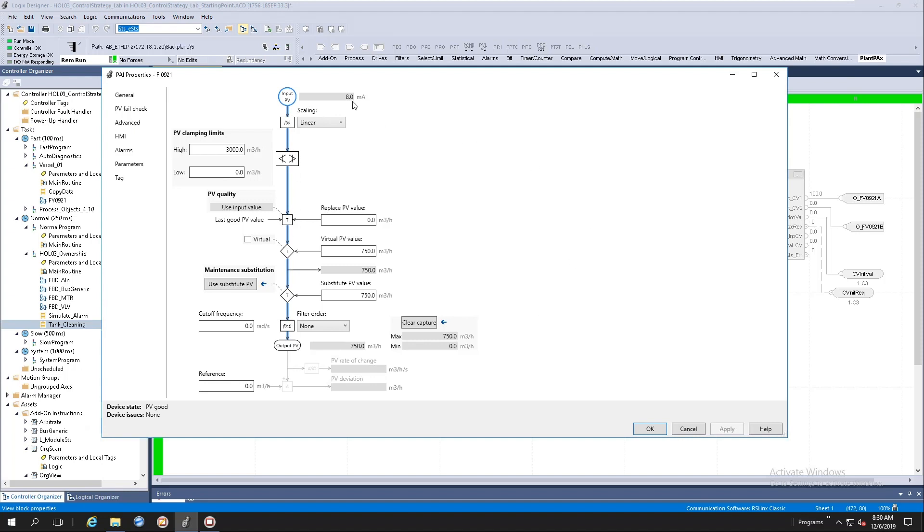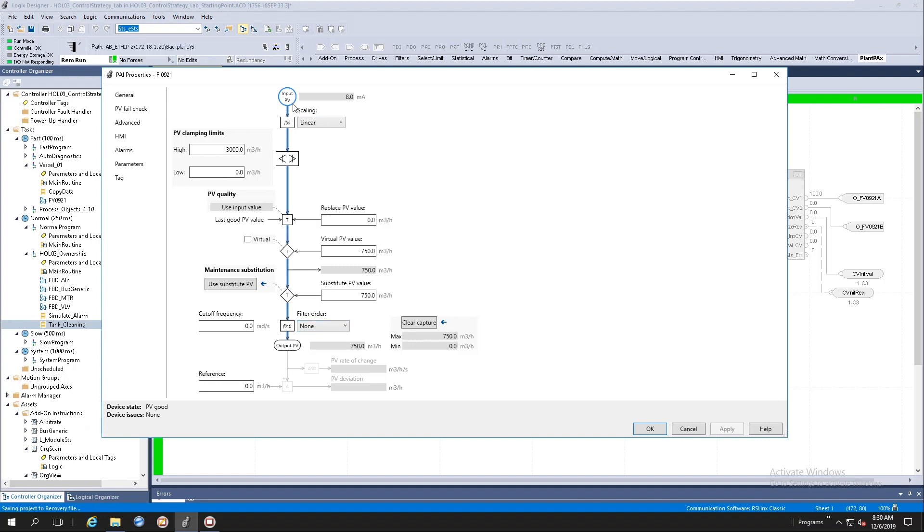Here I've got my raw 4 to 20 milliamp signal coming in. The next thing that happens is scaling. After that we will have clamping. We've got some substitutions happening here. We've got a filter ordering here and then eventually we've got our output value. Notice that we've got a blue line going all the way down to the output value. This is animated. If I change my source for my input value, this animation will disappear.